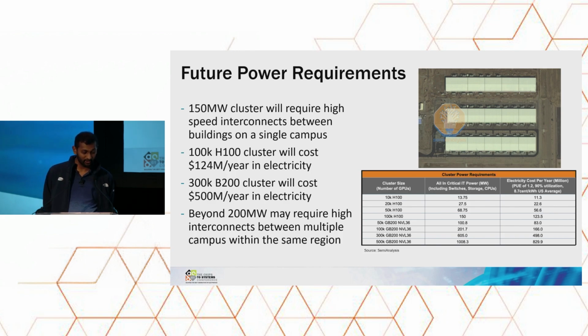And these models will come, but when you look at, for example, Elon Musk, he's tweeting about how we've already got our 100,000 GPU system being built in the next 3 months for his xAI. And he's saying next year we're going to build a 300,000 GPU system. If that's the case, then those GPUs are much more expensive, much higher power, and there's more of them. That's going to consume 600 megawatts, not 150, and that's going to cost $400 million a year to operate, again at 5 cents a kilowatt hour.